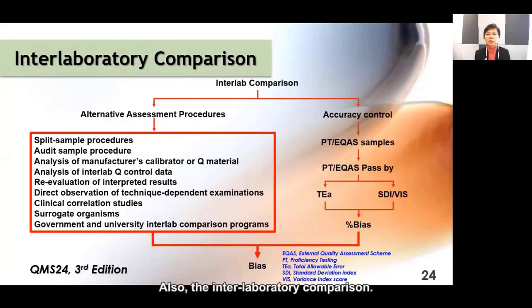Also, the inter-laboratory comparison. Usually you participate in the external quality assessment scheme or proficiency testing and get the bias. However, not all tests have a program. It might be a very new test or even a dangerous one, so that you cannot get the PT sample. So you can go to the alternative assessment procedure, and you can read more detail about the alternative assessment procedure in QMS24. However, examples are the split sample procedure or even analysis of manufacturer calibrator or quality material.